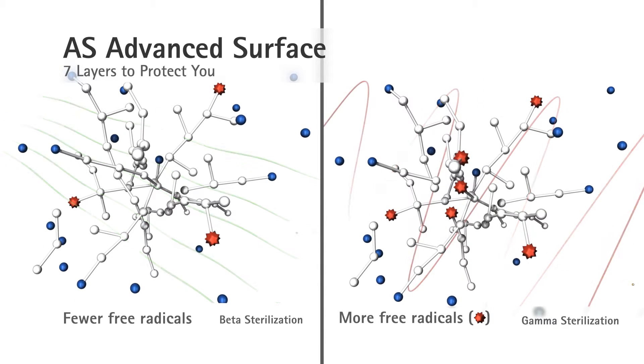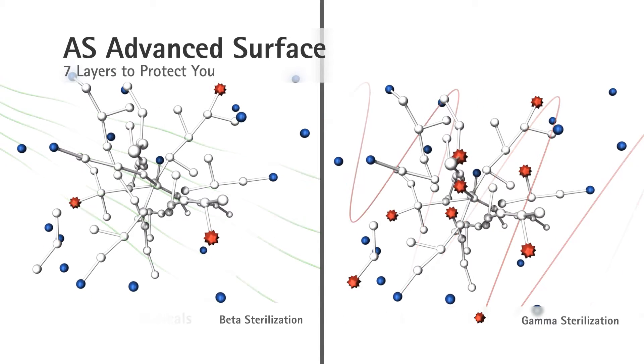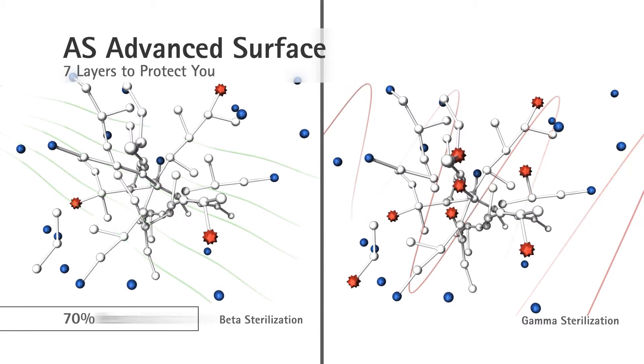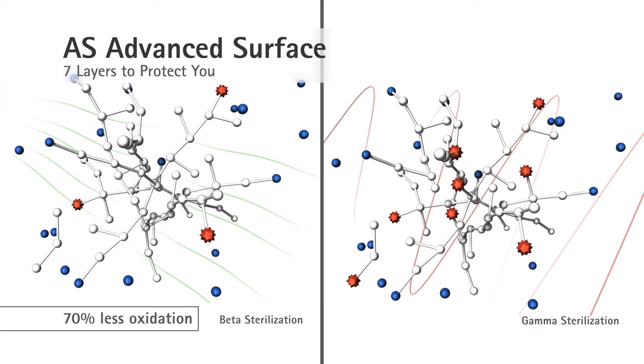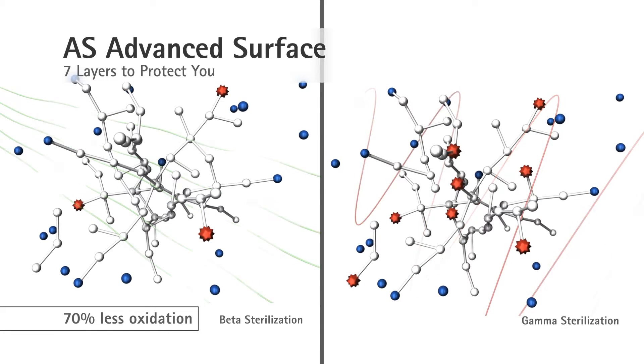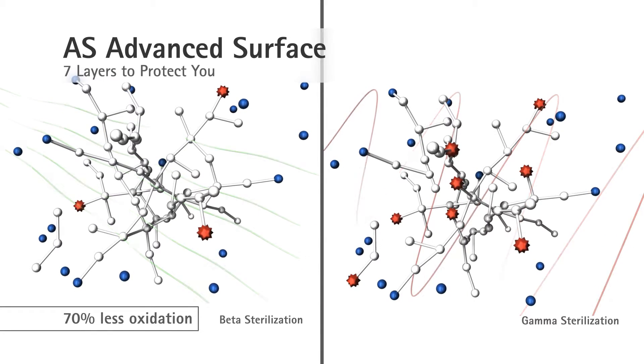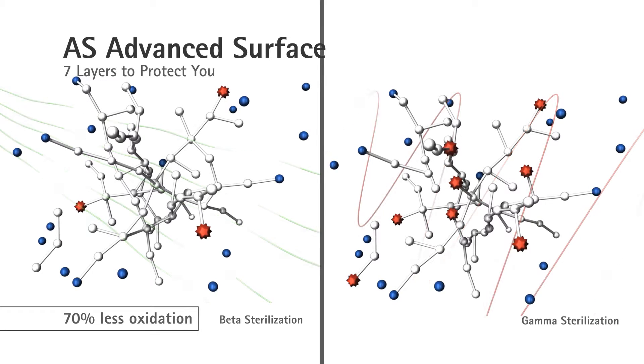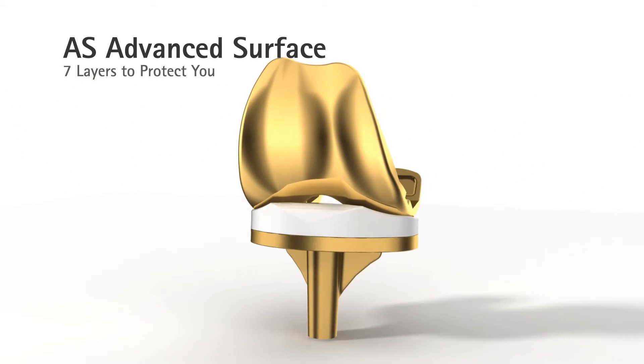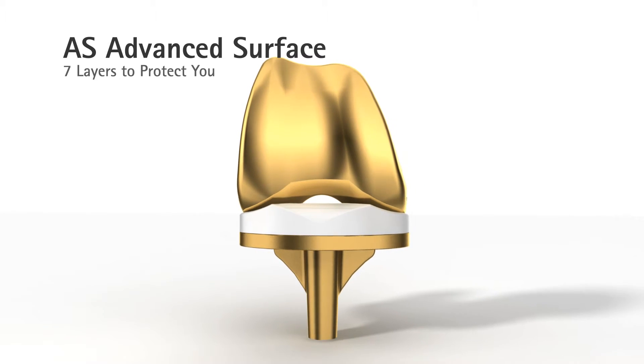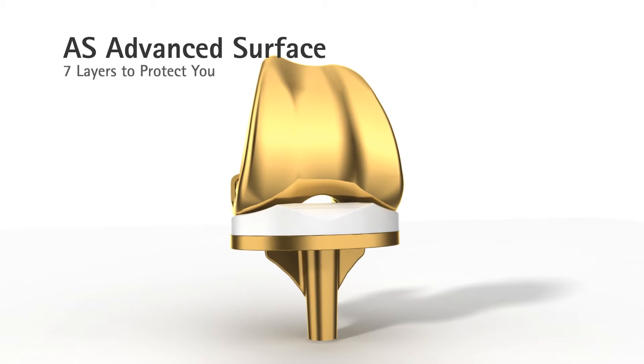Laboratory tests comparing beta and gamma sterilization found 70% less oxidation in polyethylenes sterilized using beta sterilization. Better long-term results can be expected from this combination of reduced abrasion and improved oxidation resistance.